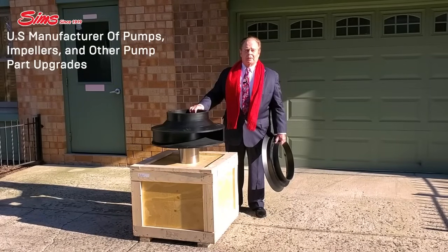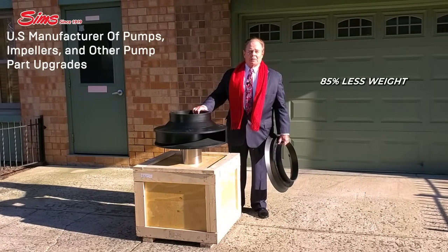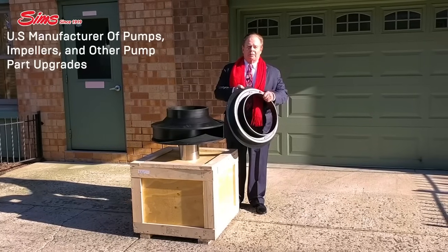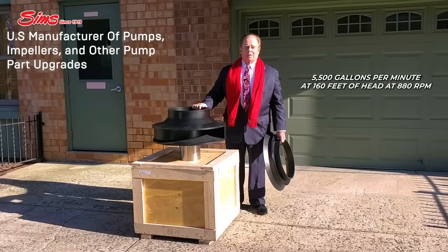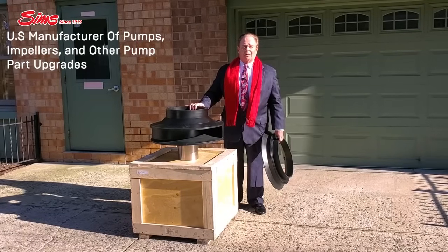This particular impeller also has the advantage of being 85% less weight. We also redesigned and re-engineered the casing ring so the rags won't clog in the casing ring area. This impeller is designed for 5,500 gallons per minute at 160 feet of head, operating at 880 RPM.